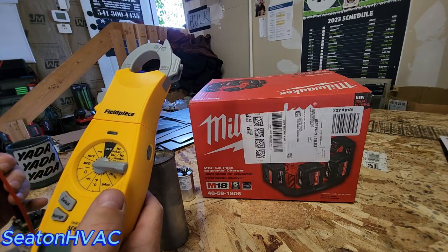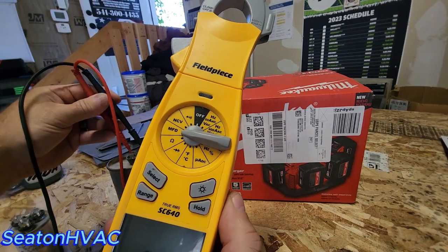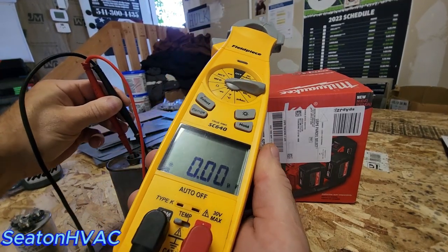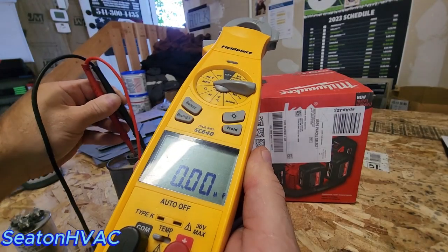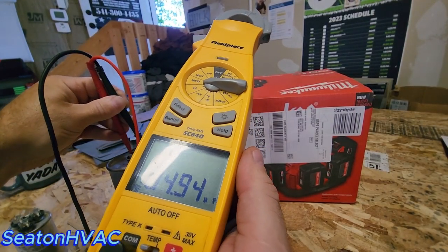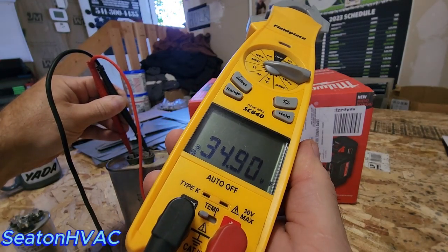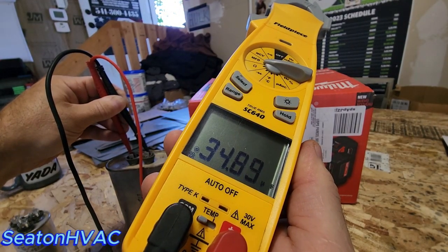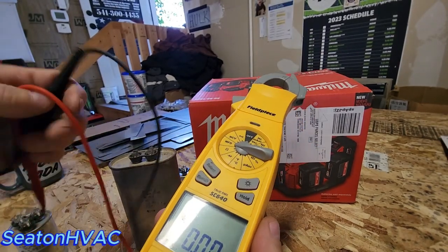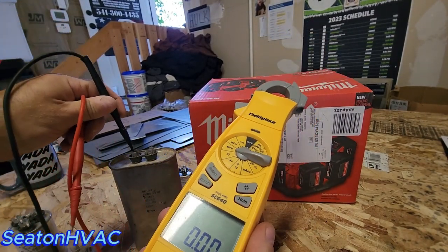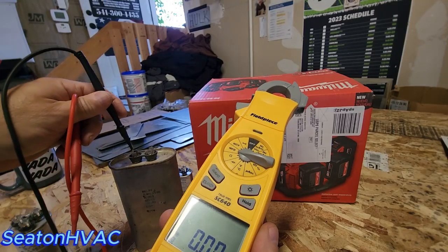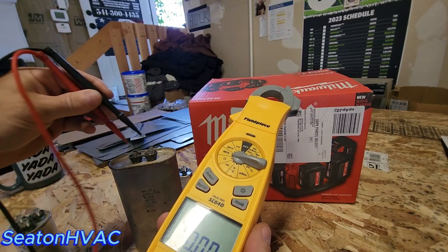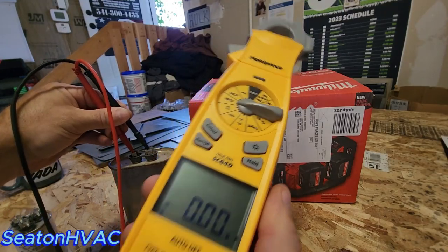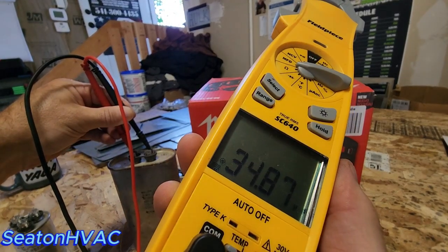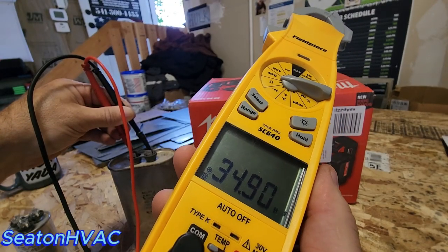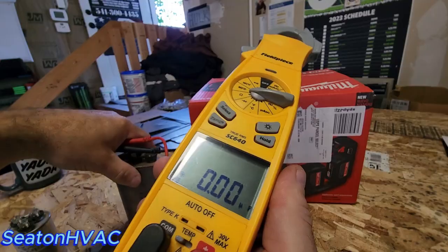Sorry, guys. All right, let's go back over here. Okay, so that's interesting. Oh, there we go. I don't know why that wasn't working. 34.9. 34.9 on a 52-year-old capacitor. So this will be on a single capacitor like this, where you're just testing one. It doesn't matter what side your leads go on, because one side's going to be your common and one side's going to be your compressor. So there you go, 34.9 on a 52-year-old capacitor. Lovely. Okay, so that's how you test that.